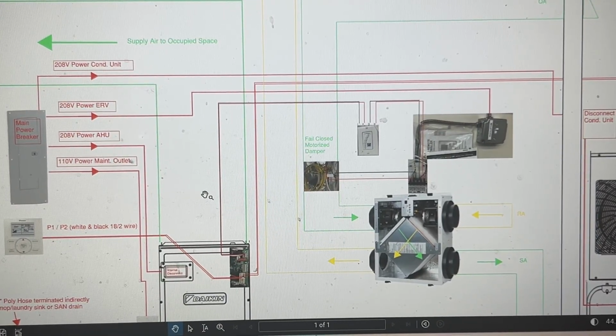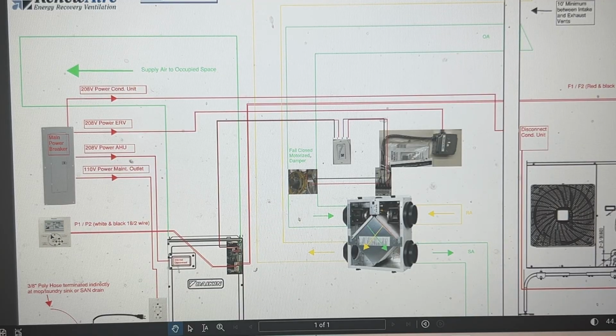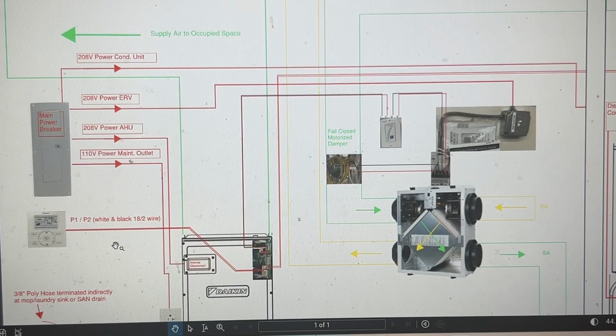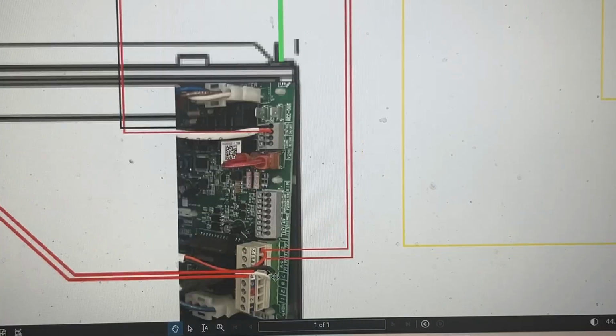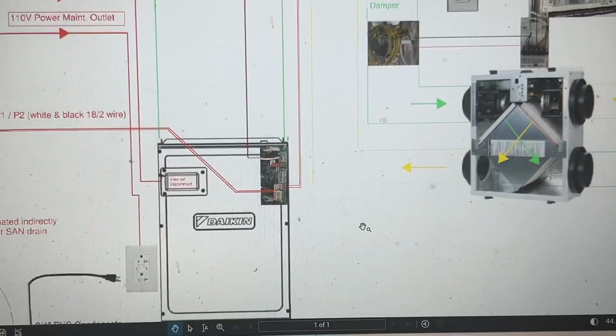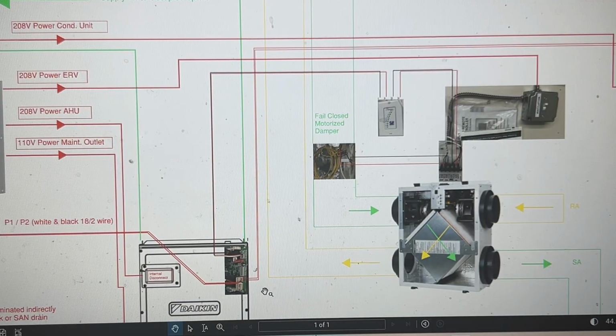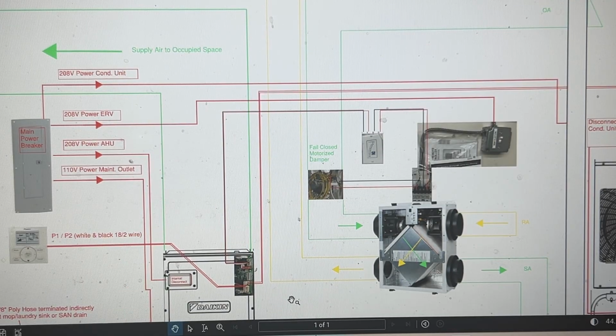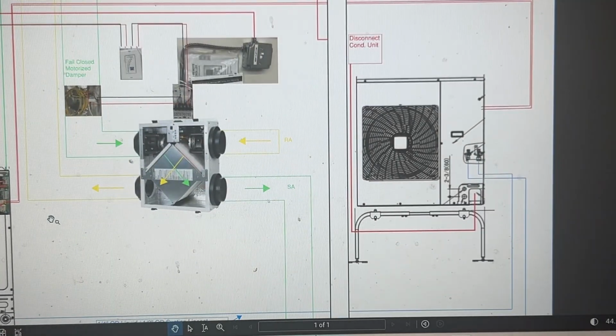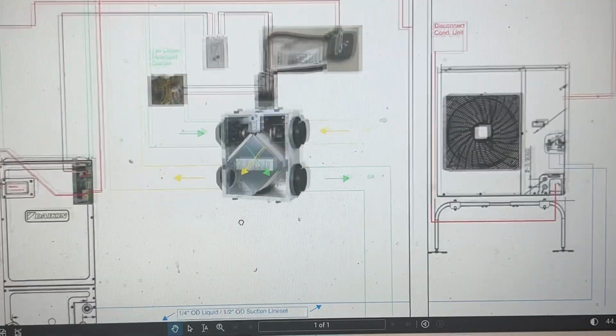All right, so for control wiring, the unit's down in the basement. The thermostat is up in the living space on the first floor. That thermostat gets mounted on the wall up on the first floor, and then 18/2 wire is run to the P1 and P2 terminals down here at the air handling unit. Then other control wiring is the F1, F2, which is another 18 gauge 2-wire run. That's the communication between the indoor air handling unit and the outdoor condensing unit. So that's how those two talk to one another.